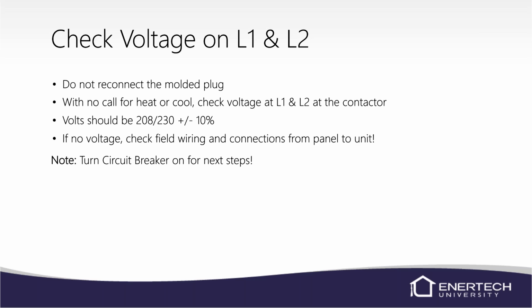Make sure you check voltage at L1 and L2. You can go ahead and pull that molded plug off with the breaker off now still and leave it off. Go ahead and give the unit voltage, so turn your breaker back on. Obviously, if the breaker immediately trips with the high voltage molded plug from the compressor removed, then there's probably something in the wiring that is rubbing, maybe a copper line somewhere, but you've got a direct short to ground and it's in the wiring somewhere because we're not hooked up to the compressor itself.